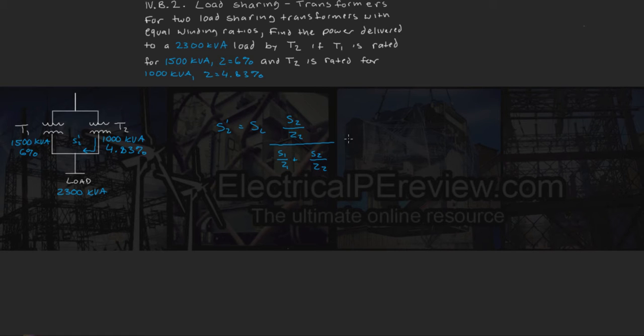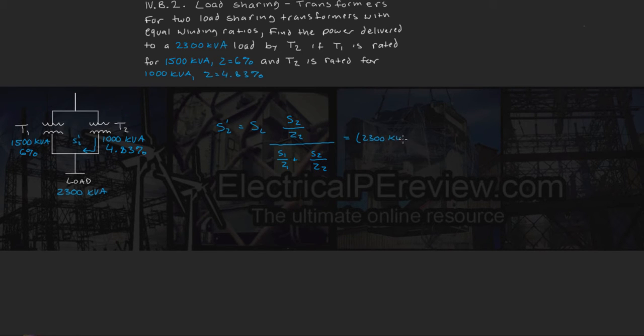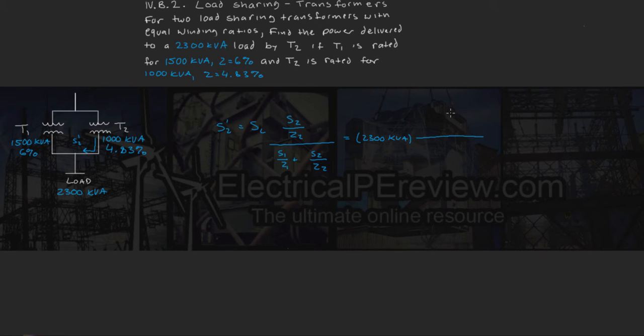So we plug in our values, and for SL, our load, we know it's 2300 kVA. And then on our ratio, we've got our S2 rating is 1000 kVA divided by the impedance, which is 4.83%.